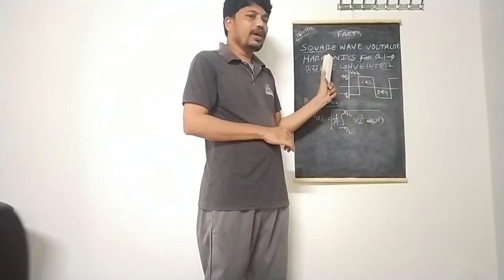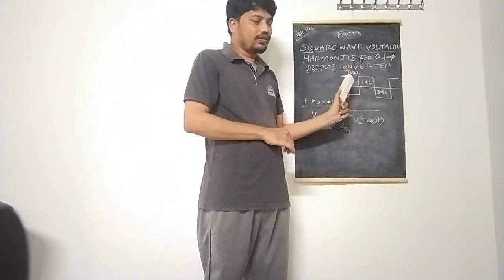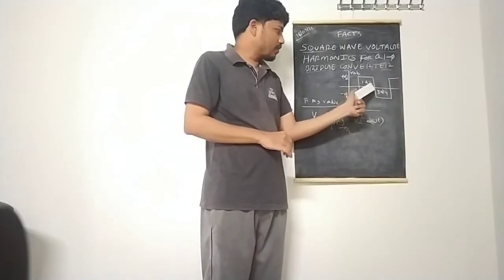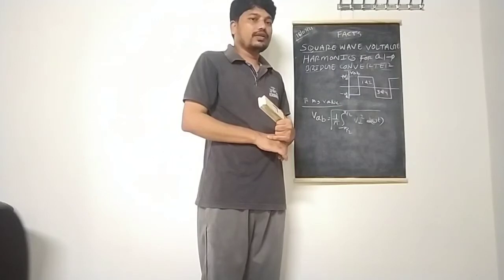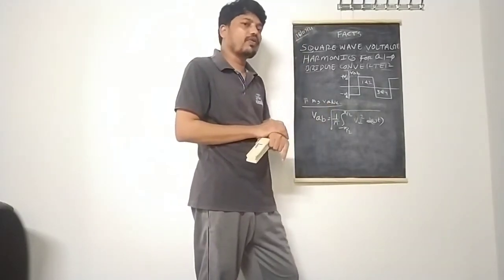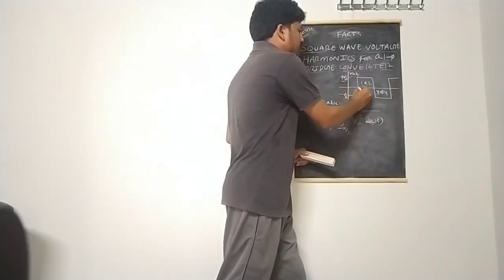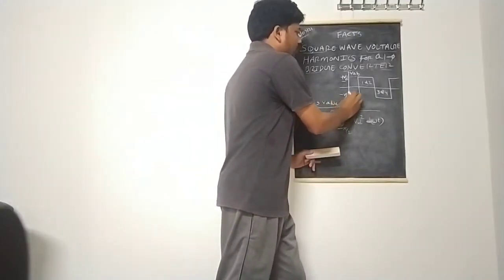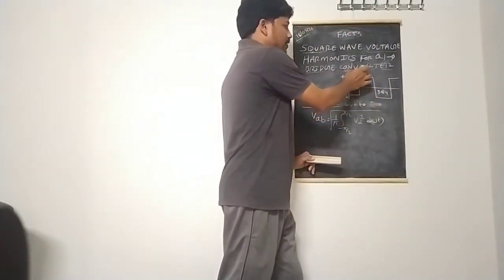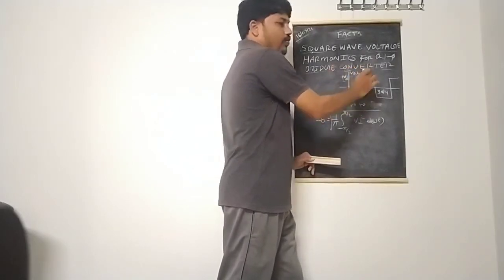We have a bridge converter diagram showing the output AC waveform, and we want to find the RMS values of this voltage waveform. The output is plus VDC when valves 1 and 2 are on, and minus VDC when valves 3 and 4 are on. Because this is a symmetrical waveform, we find the RMS value of VAB with respect to the peak value of VDC. VAB is the voltage across the converter — it is the AC system voltage.